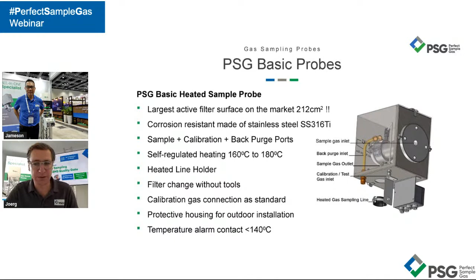So lastly, we must make sure that the sample probe is heated above the acid dew point of the gas matrix. This is the most important. Okay, thank you so much, James. I think I have to recap that a little bit, because the noise is really not getting better, unfortunately. What James just said, how he ended his speech, is that it is very important that the probe is tempered higher than the acid dew point, in order to make sure that there is no condensation happening, which is very important.